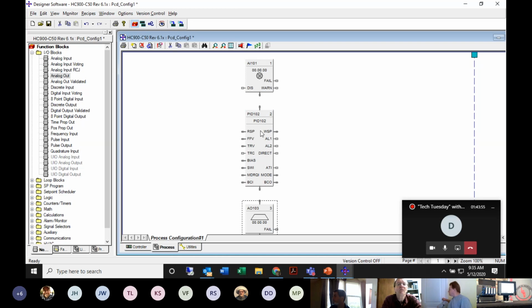Now that I have my analog input, my controller, and my analog output, the next thing I need to do is soft wire these things together so that the CPU can understand that these blocks are connected to each other. This is called soft wiring. If I double click on my output pin, you see I have a hash mark that comes up. I can connect that to the input of my PID block. Now the next step is to take the output pin of my PID block and connect it to my analog output. Now I have a PID loop that I can go in and configure.